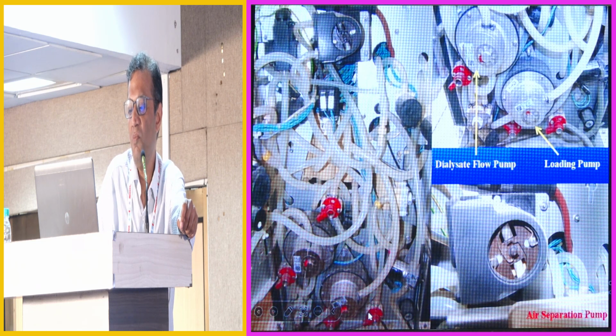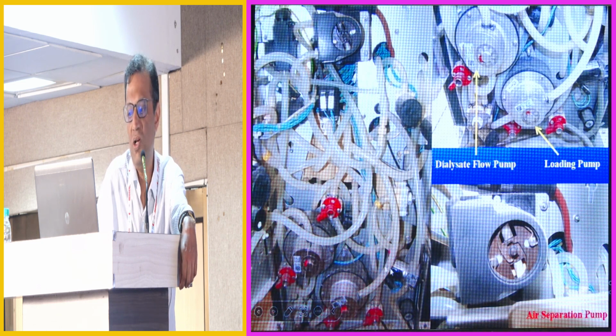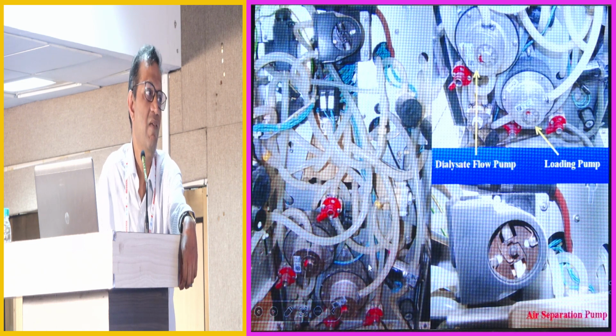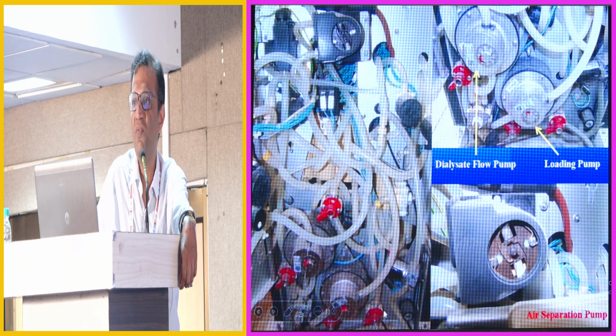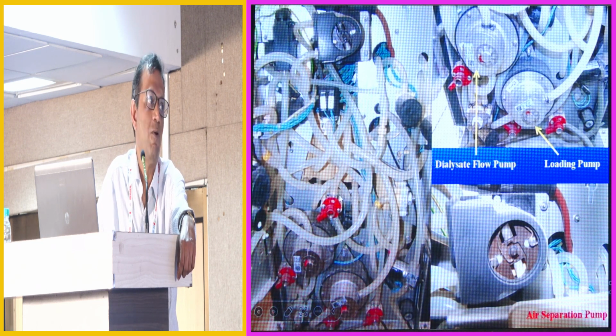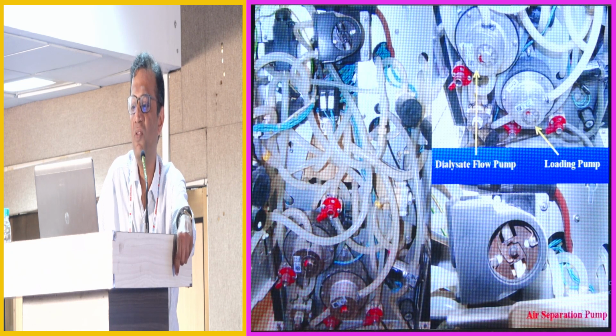So there are 4 pressure monitoring points, these red knobs over here, at which we can measure the pressure within the hydraulics of the machine. The lowest one is valve V41, which closes when the machine is switched on so that the water, instead of going to overflow, is delivered to the degassing pump. The pressure of the incoming water can be measured here and adjusted with the help of this knob. This is a negative pressure, the degassing pressure, and it has to be about -1.05 to -1.5 bar. This is the balancing chamber loading pressure, which is on the positive side of the degassing pump.